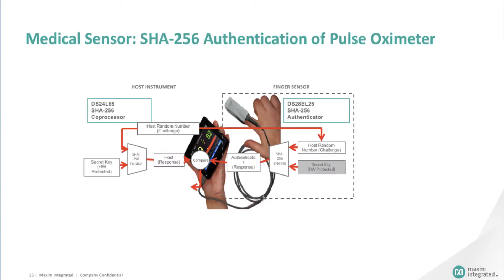As an example, let's look at how a pulse oximeter implements authentication. The pulse oximeter system has two parts: a host instrument and a finger sensor. The host system has two components: a microcontroller or FPGA and an authenticator coprocessor. The finger sensor is plugged into the host instrument, which initiates the authentication process. The micro or FPGA generates a random number and sends it to the authenticator within the finger sensor — this is the challenge. The authenticator then takes that random number, combines it with a secret key and other data, then uses the SHA-256 engine to produce a MAC message authentication code, or response — also known as a message digest.